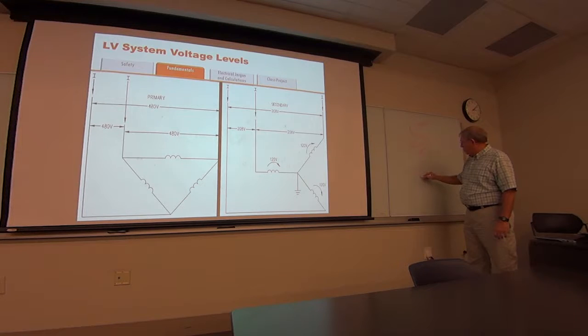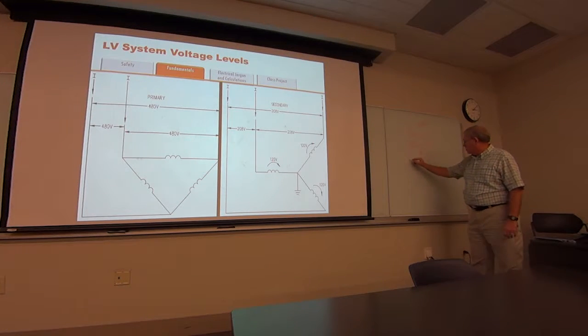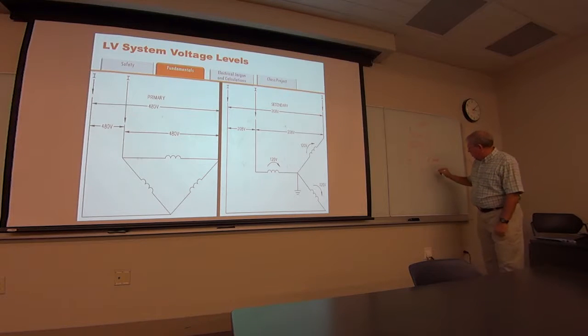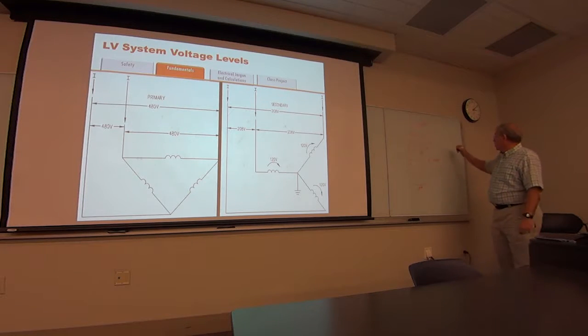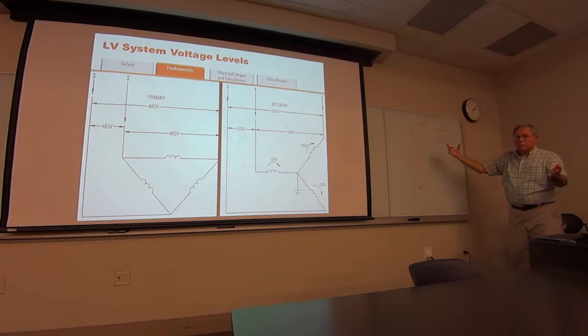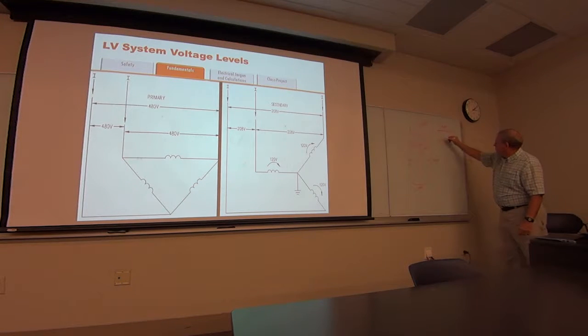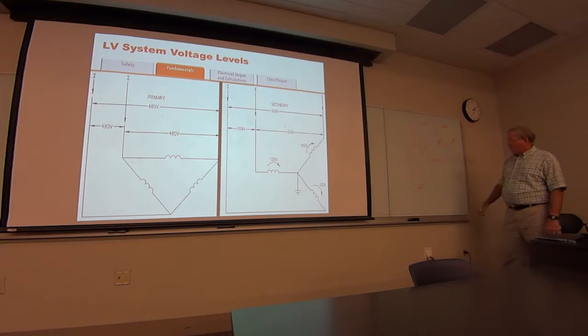So when you go into your panel, you've got a main breaker here and a main breaker here. This might be a 225 amp breaker. And between these two wires you've got 120, but you've got 240 across here, you see. So that's how you get single phase 240. Now if you're doing a three phase, this would be 240, 240. You can have any voltage you want. They all usually are the same. And then what you do is you center tap one of these, and you do the 120, 120. And if you really want to do something fancy, you can actually take this transformer out and still get three-phase 240 and 120. There's a town I had in Alabama where I managed the utility, had a lot of industries, and they just needed a little bit of three-phase. Instead of running 3 lines to them, we ran 2 and put one of these up. But is that clear?